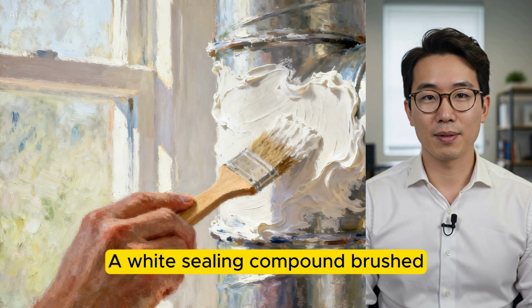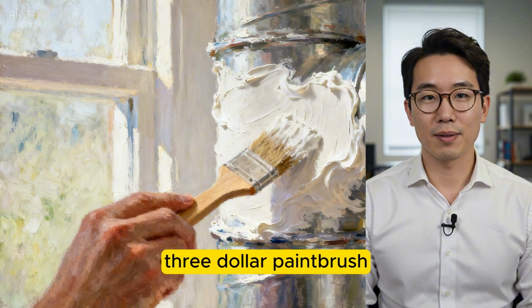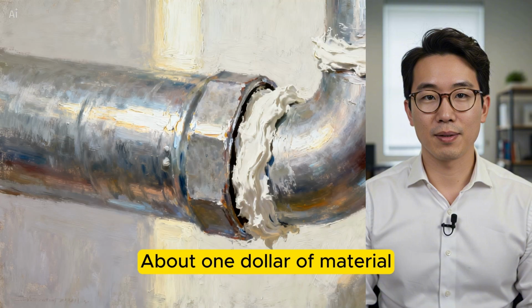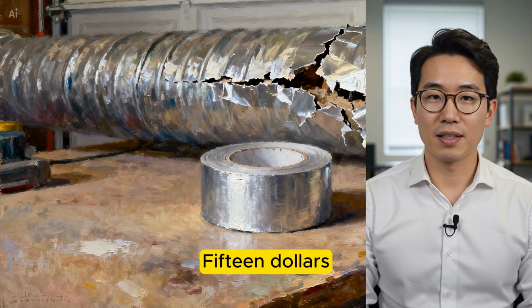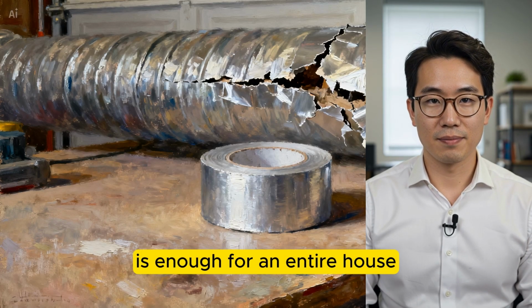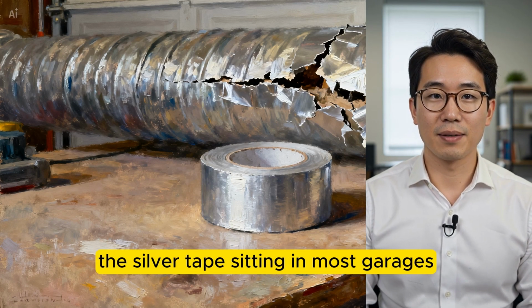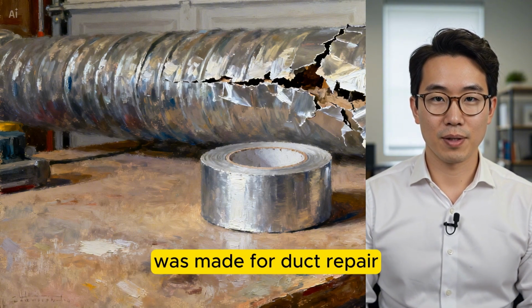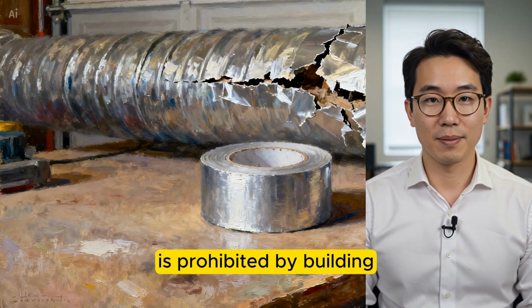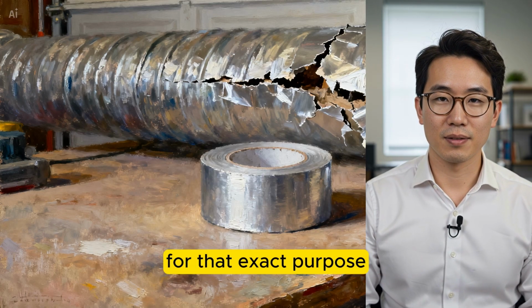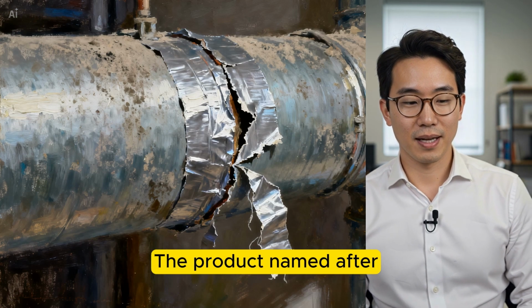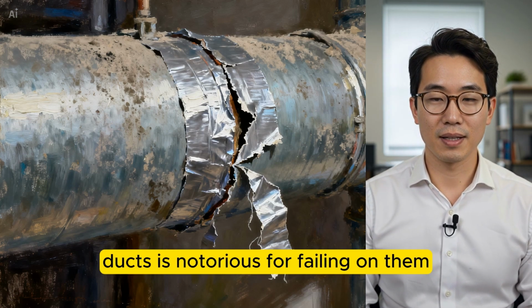A white sealing compound brushed across duct joints with a $3 paintbrush. About $1 of material seals a single connection. $15 is enough for an entire house. Meanwhile, the silver tape sitting in most garages, the one people assume was made for duct repair, is prohibited by building codes across much of the country for that exact purpose. The product named after ducts is notorious for failing on them.